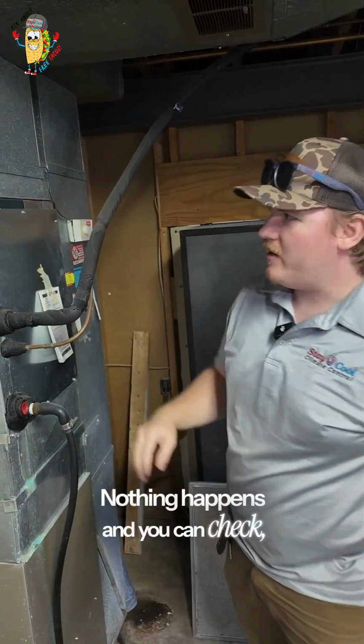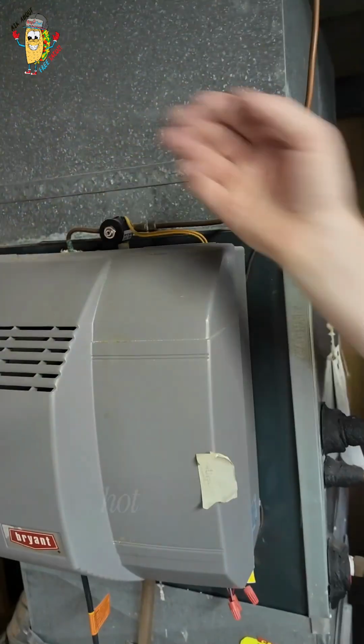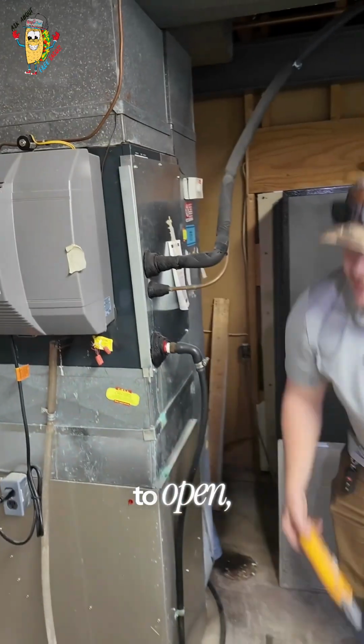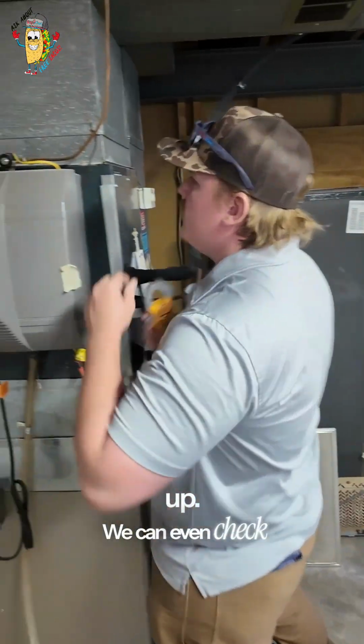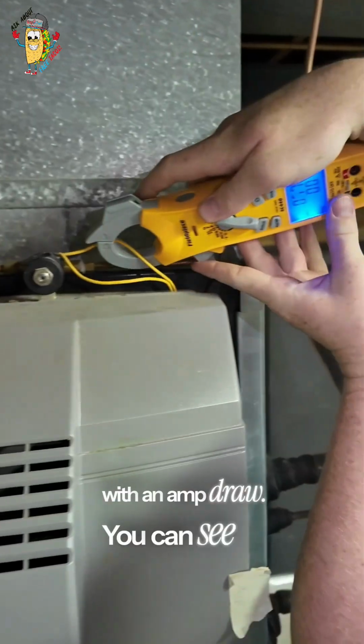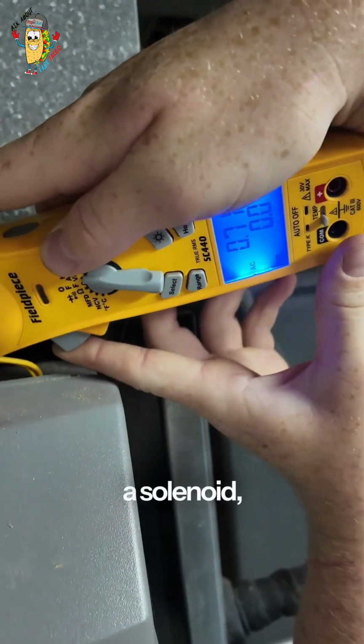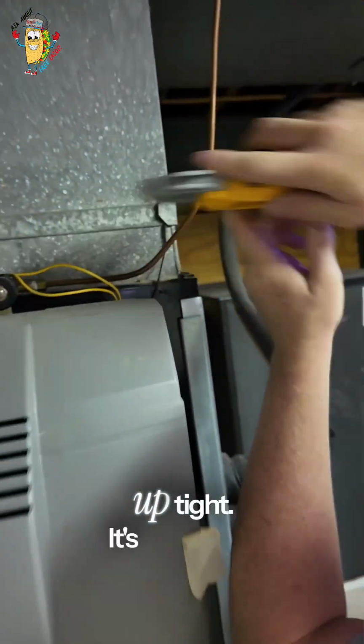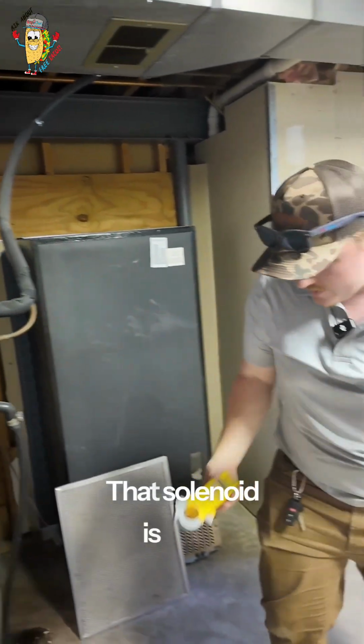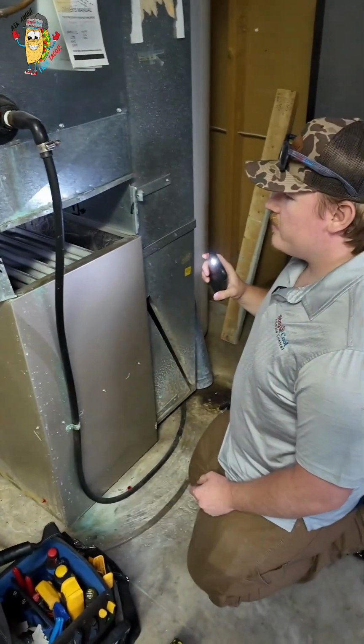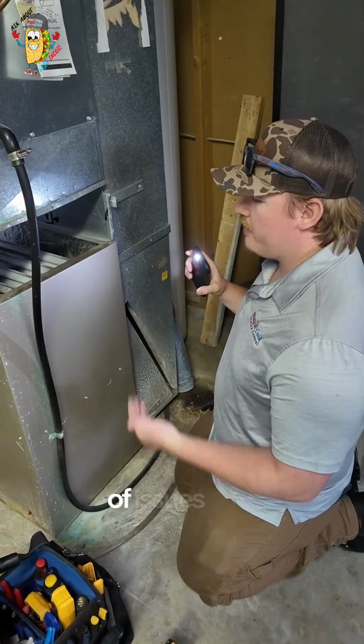Nothing happens, and you can check. You can feel this solenoid is super duper hot from the coil in there trying to open, but it's locked up. We can even check with an amp draw. You can see it's pulling pretty high amps for a solenoid, so it's locked up tight. It's not gonna let any water through. That solenoid is bad.